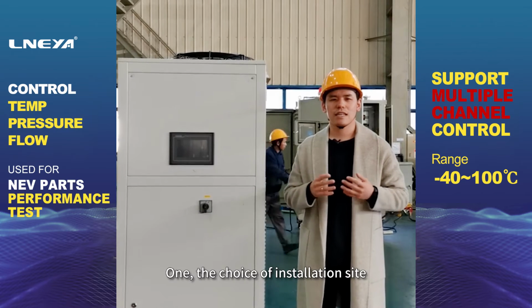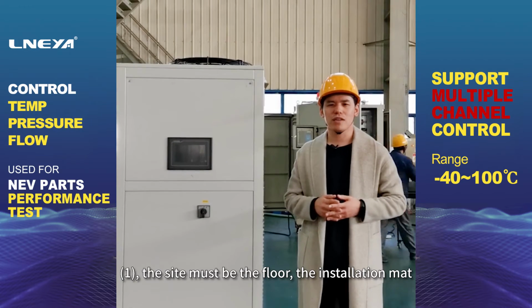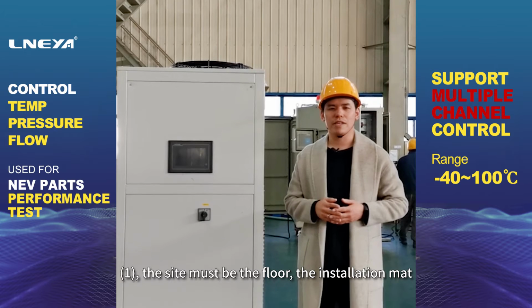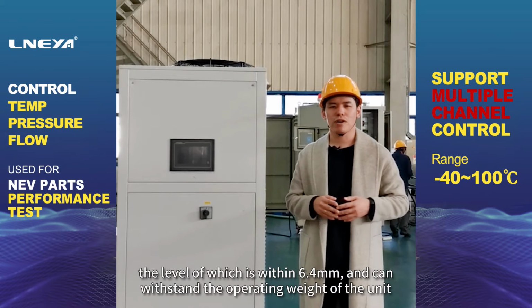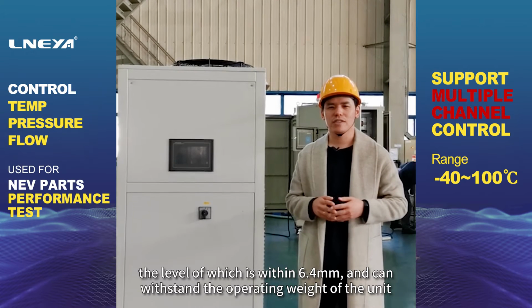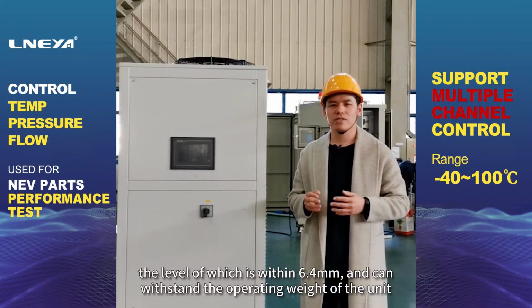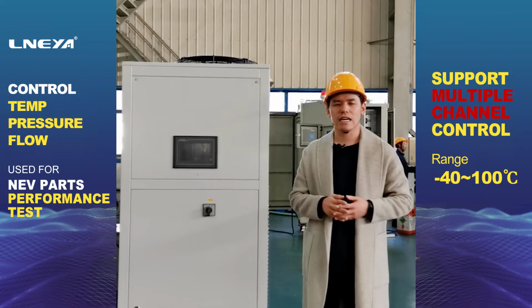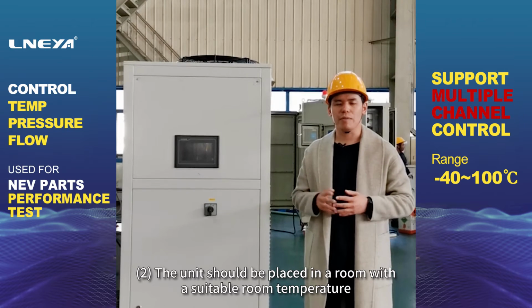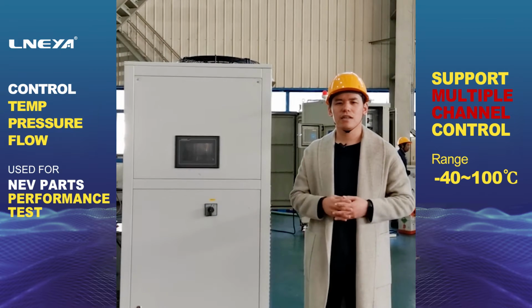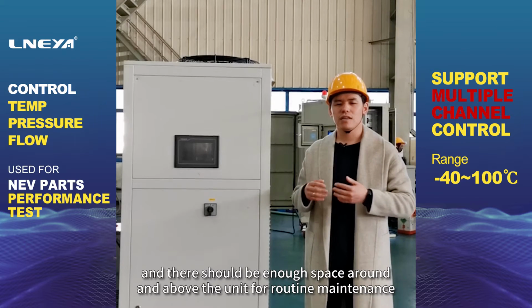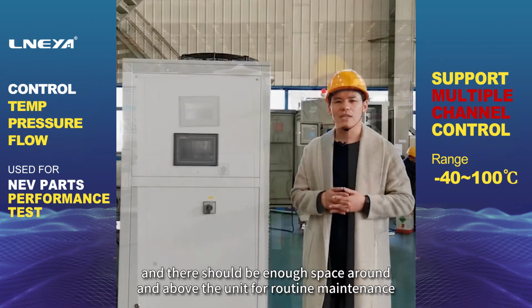First, the choice of installation site. 1. The site must be the floor, the installation mat, the level of which is within 6.4 mm, and can withstand the operating weight of the unit. 2. The unit should be placed in a room with a suitable room temperature, and there should be enough space around and above the unit for routine maintenance.